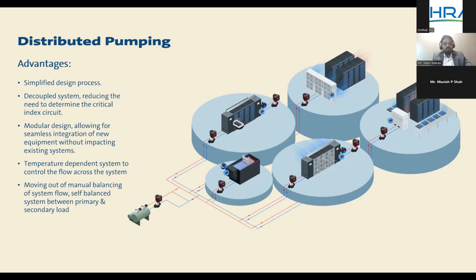We want the system to be self-balanced. With distributed pumping, and with the kind of pumps connected to each load, that's very well possible. We are clearly decoupling primary and secondary, and we connect dedicated pumps to each node. By doing that, the system becomes self-balanced, and we are moving out of a manual balancing system. These are clear advantages that we are trying to add with distributed pumping on top of the conventional system we have today.